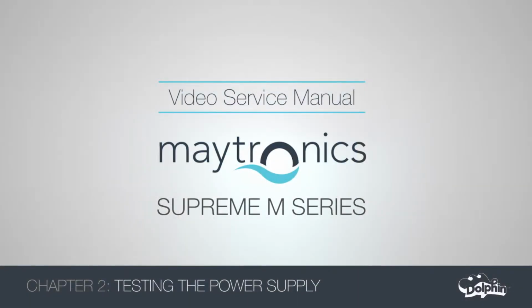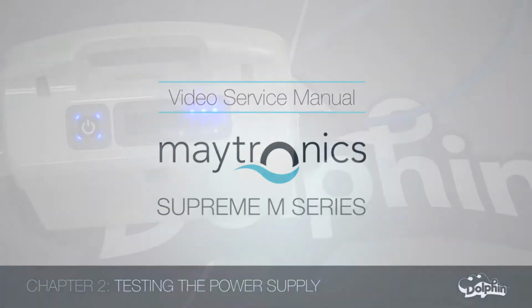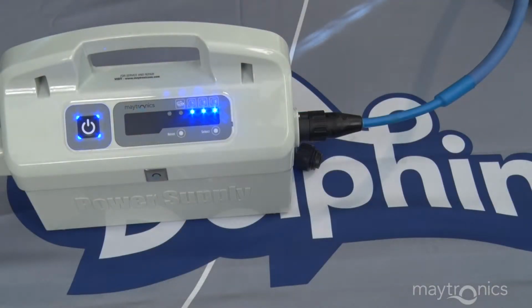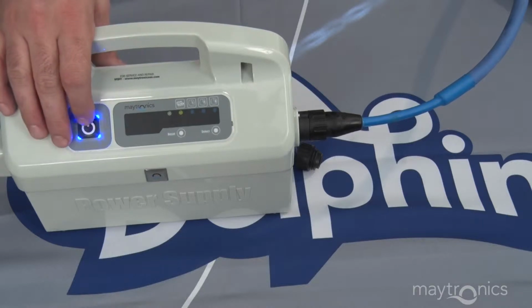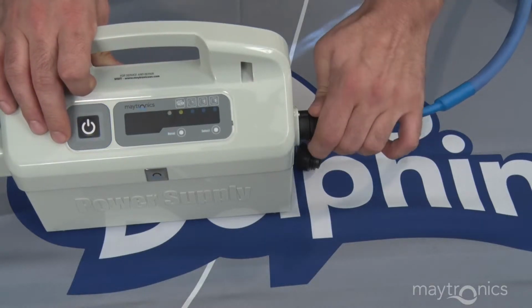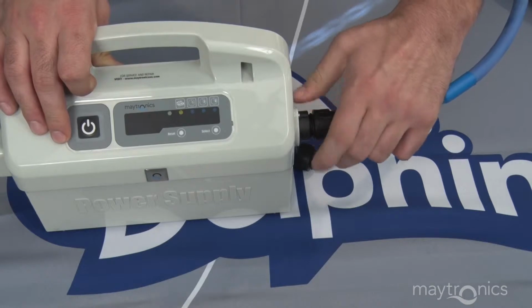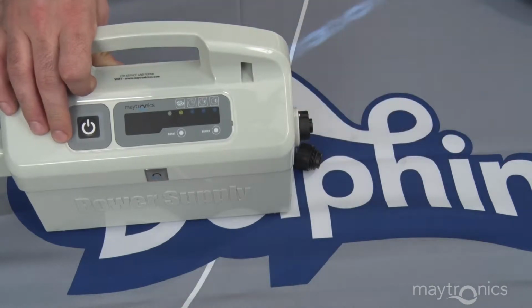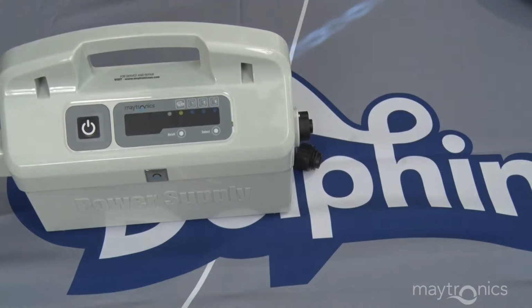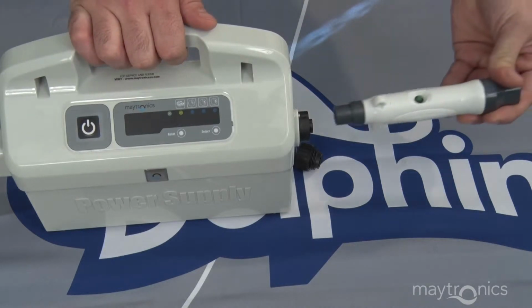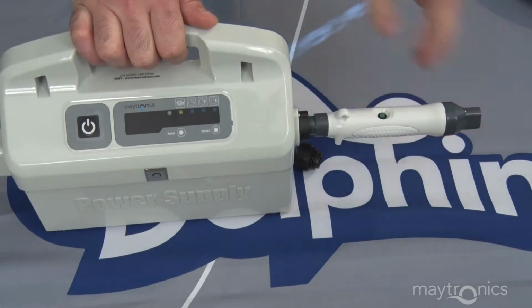Chapter 2. Once you have completed the unit's self-test cycle, you should now proceed with testing the unit's major components. First, test the power supply. Begin by unplugging the floating cable from the power supply and inserting the round end of the Dolphin tester into the Amphenol plug socket. Turn the power supply on.